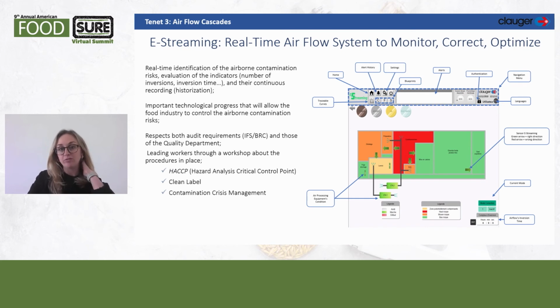E-streaming uses velocity sensors to detect not only the direction of the airflow, but also the pressurization needs for the dynamic areas. These sensors can detect airflows from a minimum speed of 0.05 meters per second, and this precise reading allows the air handling units to be ramped up or down based on the processing mode or actual needs. This not only ensures food safety, but can also result in significant energy savings.